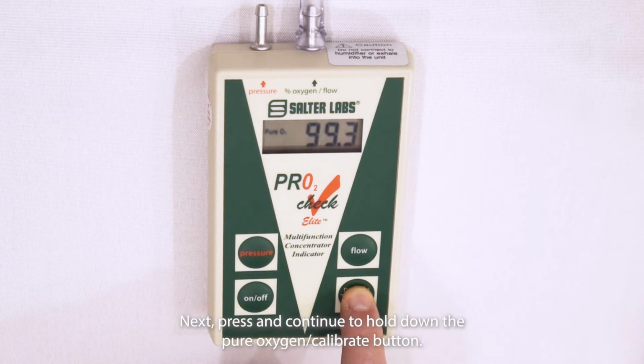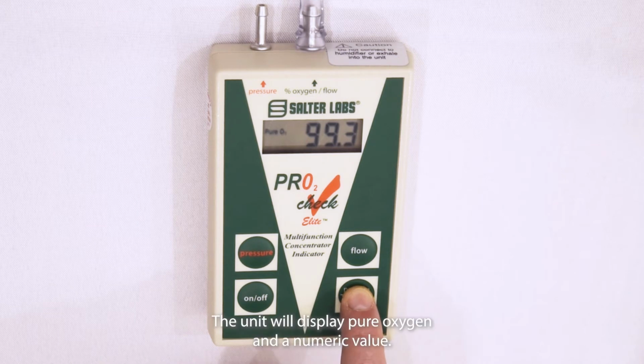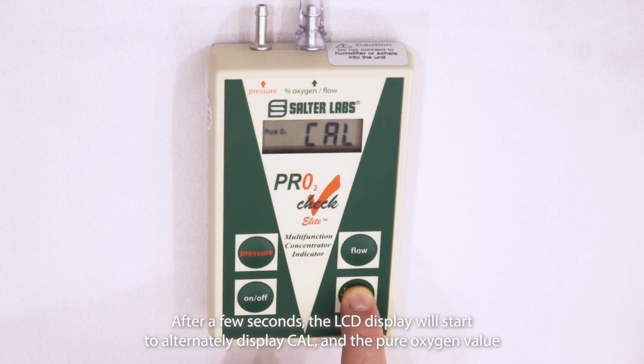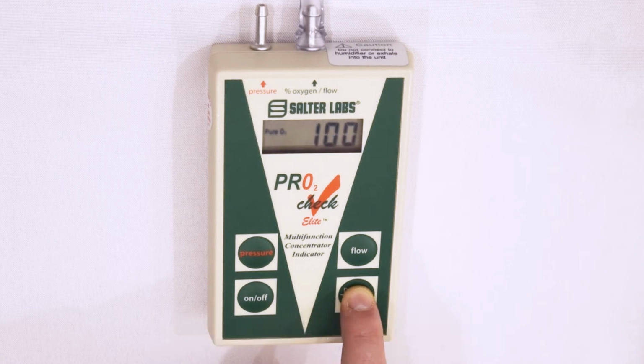Next, press and continue to hold down the Pure Oxygen Calibrate button. The unit will display pure oxygen and a numeric value. Continue to hold down the Pure Oxygen Calibrate button. After a few seconds, the LCD display will start to alternately display Cal and the pure oxygen value.